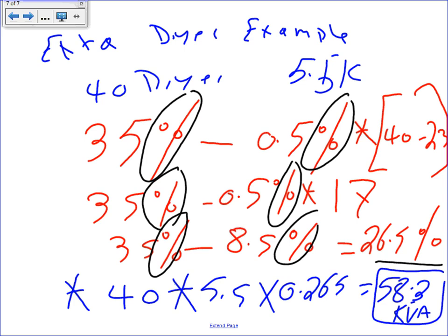Now, Ashley was saying you can multiply this by 35 from the get-go. Be my guest. You could do 40 times 35, then 40 times 5.5 times 35, multiply, and subtract, and that's fine. When we do it, I teach this one, guys, for the example for the state. You always find the derating factor, then way at the end you apply the derating factor to the total. I think it's the easiest way. If you have a different way of doing it, by any means do it.